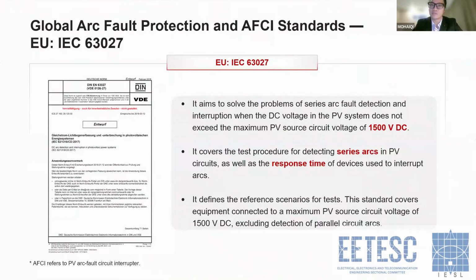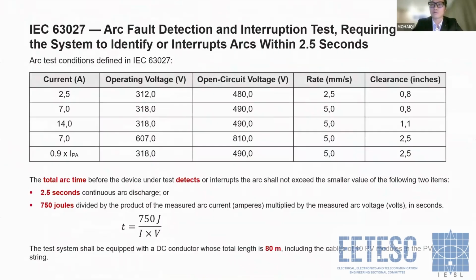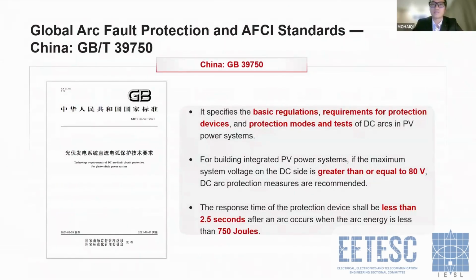These are some standards for the AFCI function. One is IEC 63027, which is more globally used for PV. This standard covers voltages up to 1500 volts DC. It also requires the identification and disconnection time to be within 2.5 seconds, along with a power or energy requirement. Another one is the Chinese standard GB/T 39750, which refers to the IEC standard to give some suggestions. The minimum requirement is that if your system's DC voltage is more than 80 volts, then you should follow this standard.